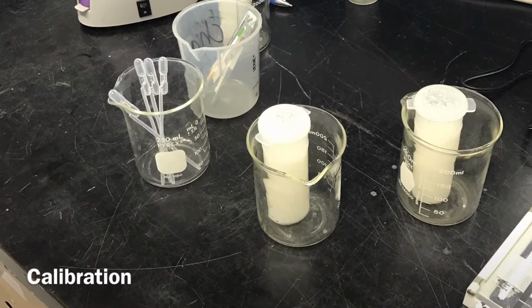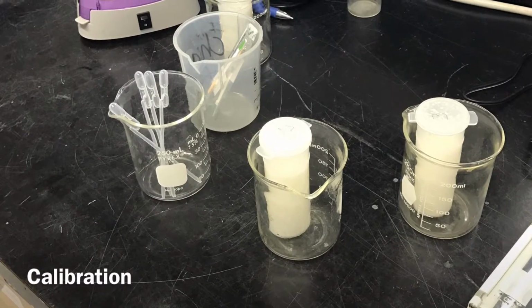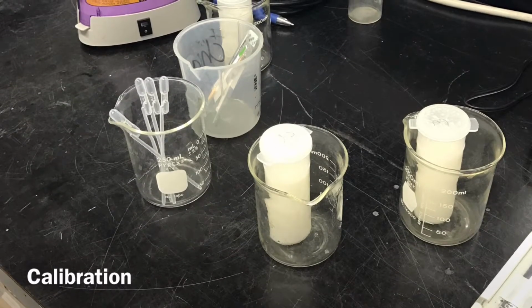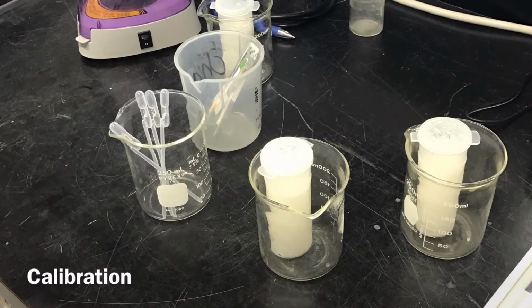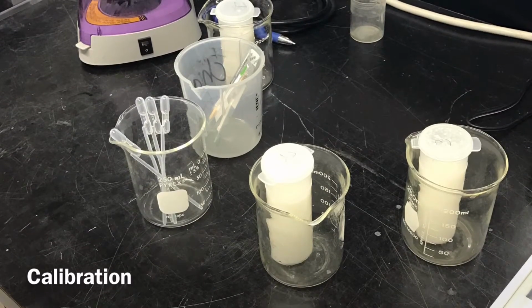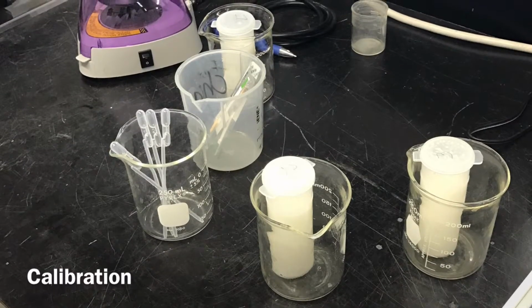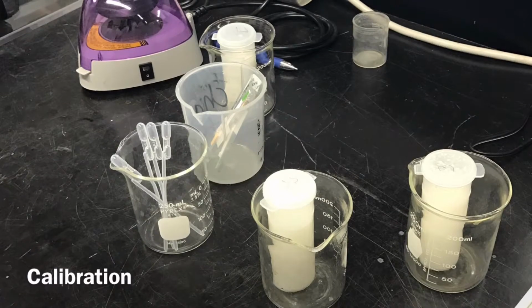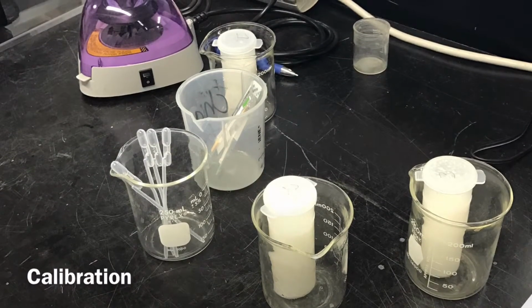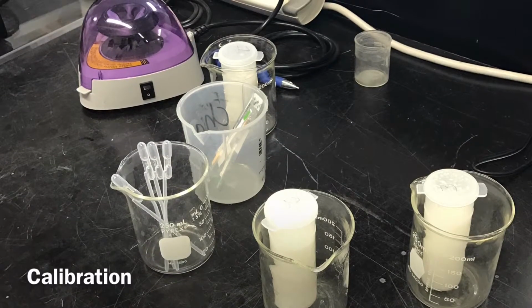The controls in this example were frozen, thawed, and then centrifuged. The Charm machine is calibrated with positive and negative strips, which set the limits of the antibiotic residues. The machine is then tested against the positive and negative controls. If the controls are read correctly, the machine is now ready to be used with the new samples.